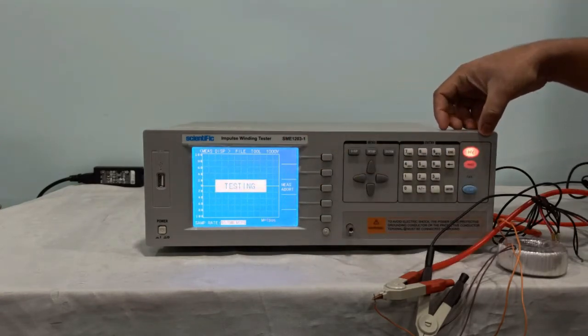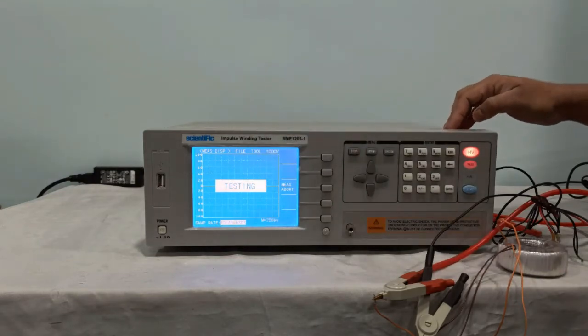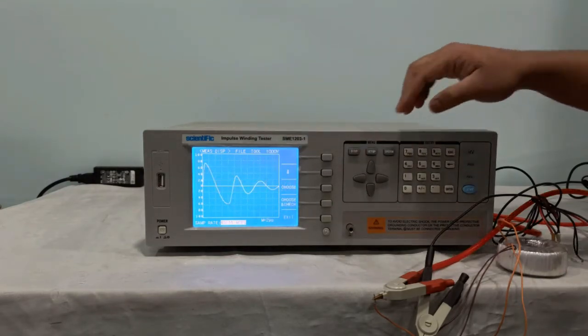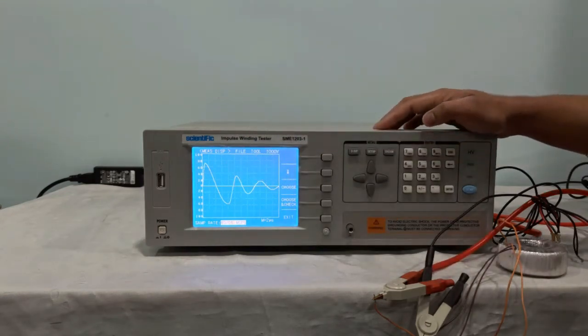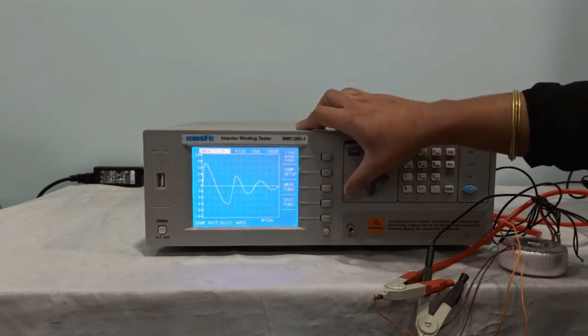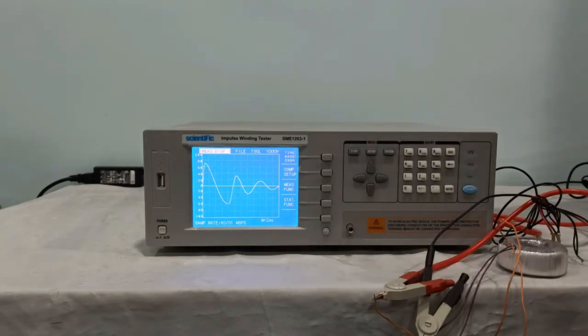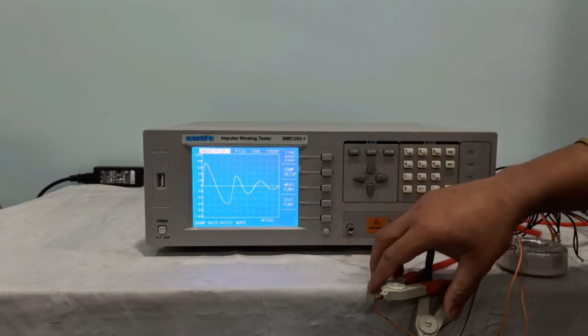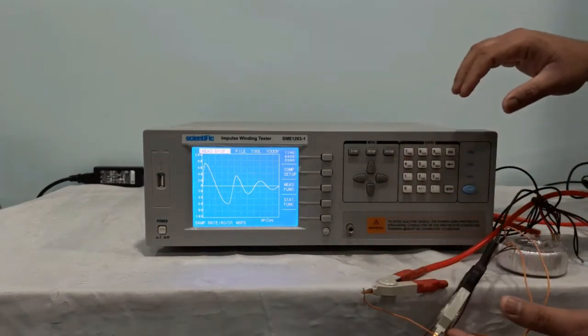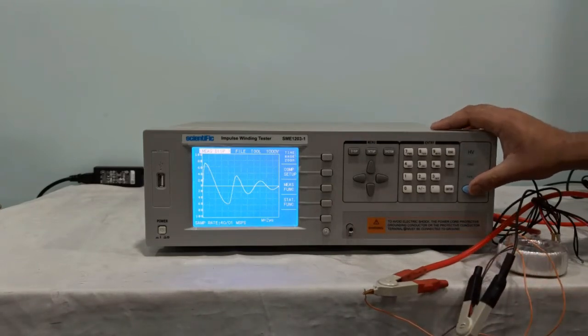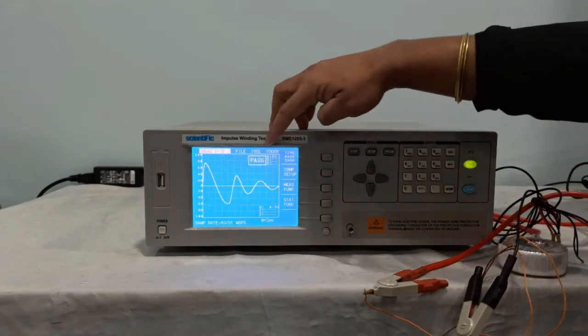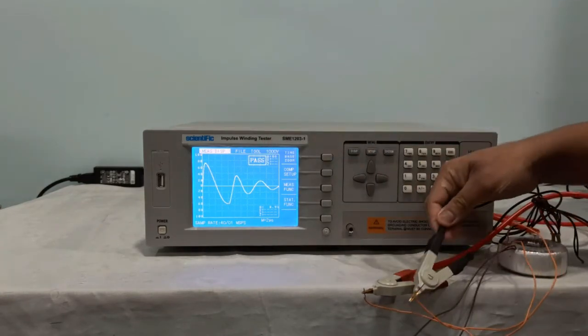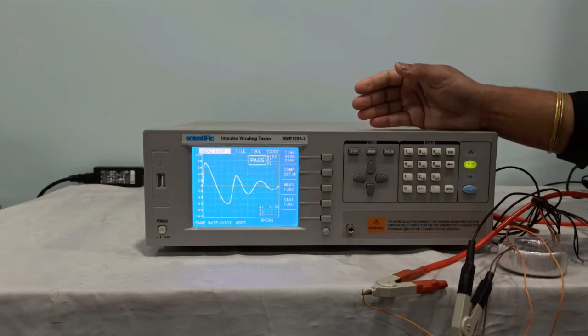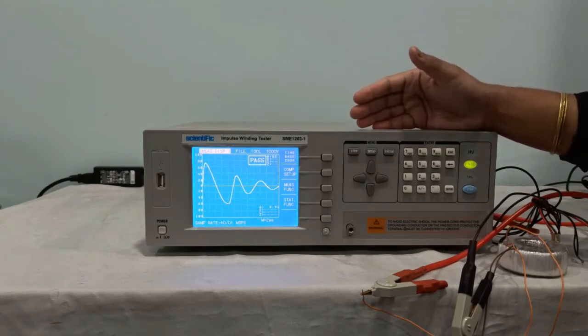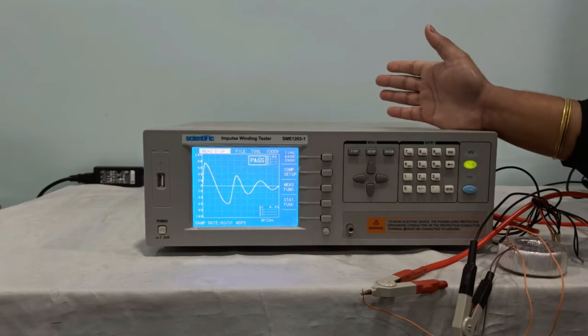Now see, HV LED is glowing and testing is displayed on screen. After the testing is done, you can find a waveform here. So this is the standard waveform. We'll select choose. Now your standard waveform is selected. Now you can check by changing the DUT whether your result is pass or fail. Right now we are not changing, we'll just see. Now you are getting result as pass, as we have not changed the DUT, so the standard waveform and the tested waveform are the same. So you are getting the result as pass.